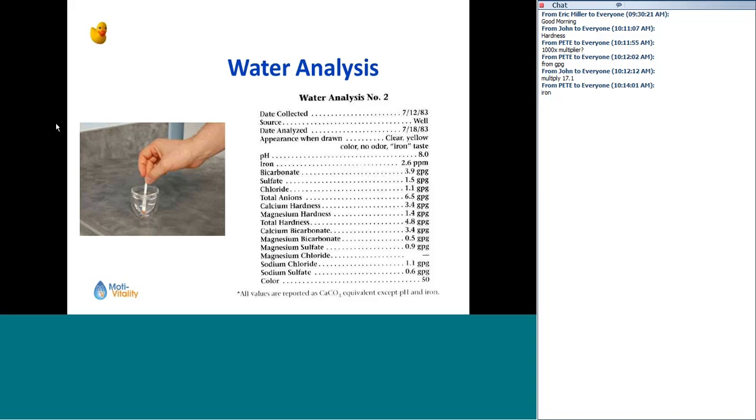Okay, so usually clear water iron stays clear if your pH is slightly lower, acidic, because it stays dissolved. With a pH of 8, you usually have an excess of hydroxide in the water. Those extra hydroxides could be sticking to some of that iron and causing it to convert from its ferrous form to its ferric form. So we need to bring the pH down. Also, 8 is pretty high there.